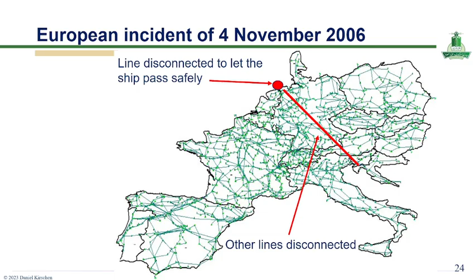During the European incident of 4 November 2006, a transmission line in Germany was intentionally disconnected to allow a large ship to pass safely under a river crossing. This planned action was expected to be within normal operating limits. However, the disconnection caused an unexpected redistribution of power flows across the interconnected European grid. As a result, other transmission lines became overloaded and were subsequently disconnected by protection systems. This sequence of events initiated a cascading effect within the network, demonstrating how a single planned switching action under certain conditions can lead to widespread instability if system conditions are already close to their limits.